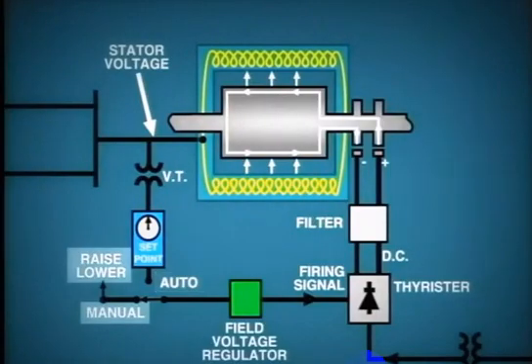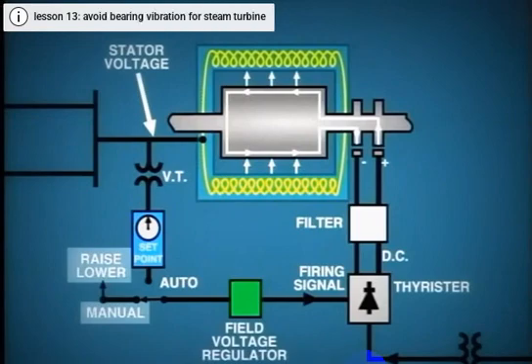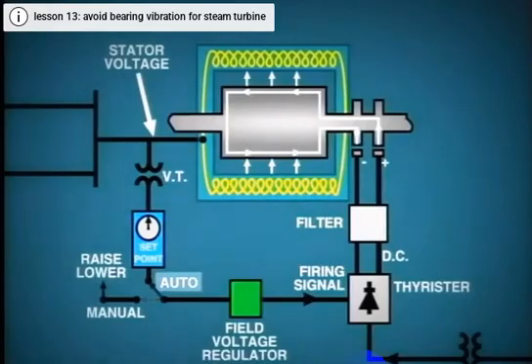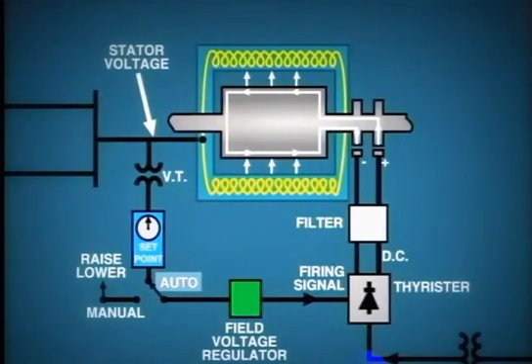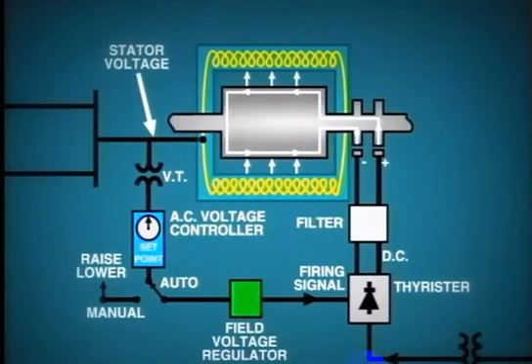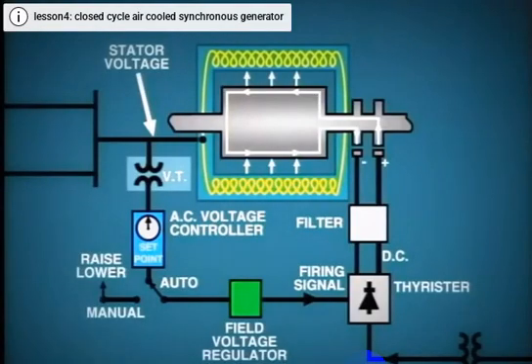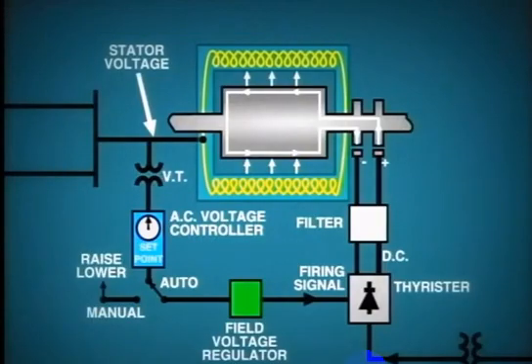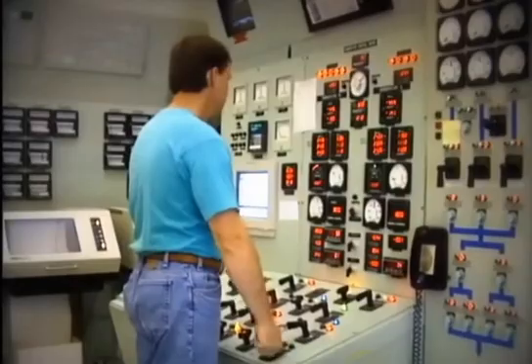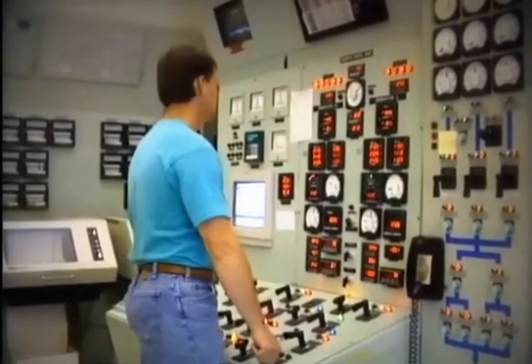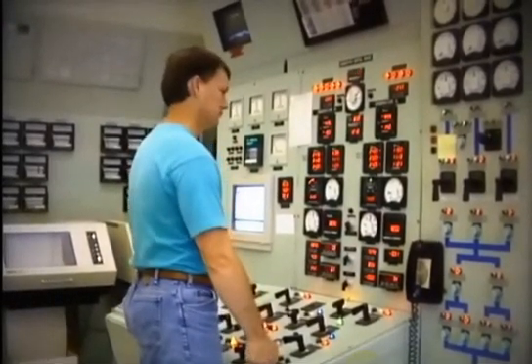The manual control disconnects the automatic function and allows the operator to directly control excitation. However, when the generator is in operation, the field voltage regulator is usually controlled from the auto position — that is, from the AC voltage controller. This controller monitors the generator bus output voltage through VTs and automatically adjusts excitation to maintain the setpoint voltage. The operator can adjust this setpoint and thus exercise control while the excitation system is operating in auto.